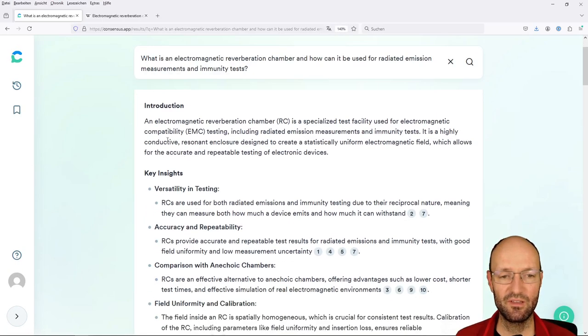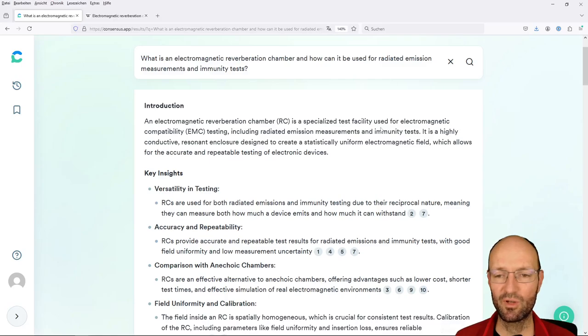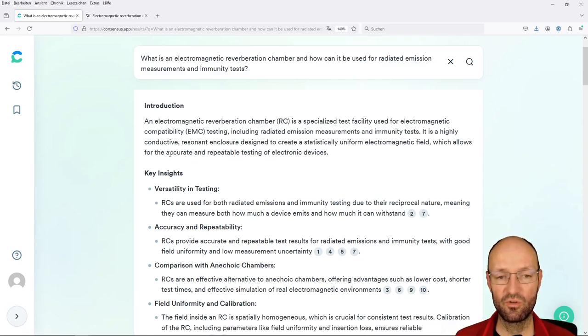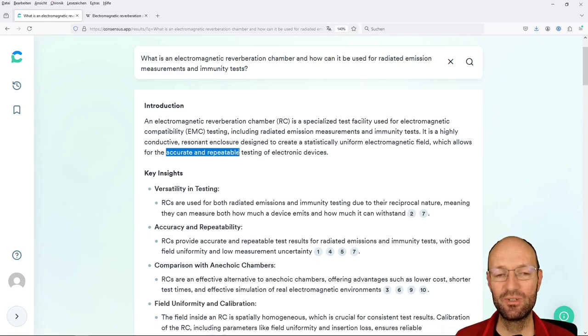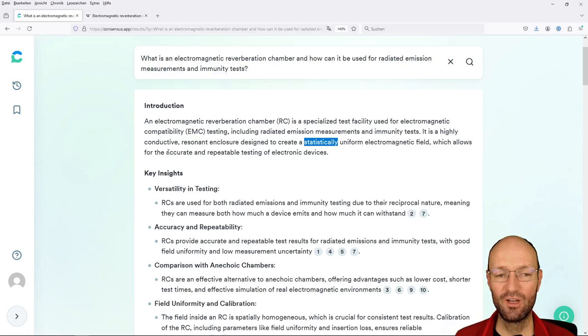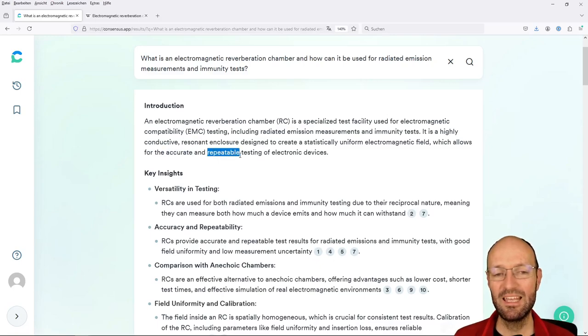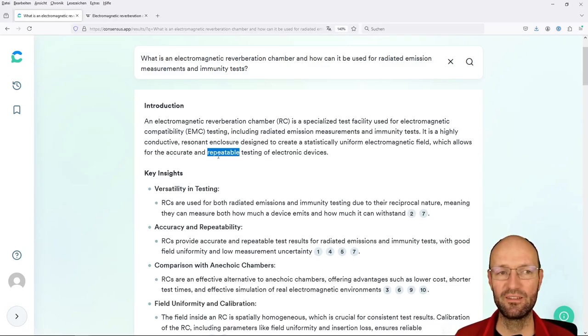Let me enlarge this a little bit. So it says as an introduction, a reverb chamber is a specialized test facility used for electromagnetic compatibility testing. This includes radiated emission measurements and immunity tests. It's repeating my question. And it is a highly conductive resonant enclosure designed to create statistically uniform electromagnetic fields. That's correct. Which allows for accurate and repeatable testing of electronic devices. And I would doubt and I would question the really accurate and repeatable because in the end, it's a statistic test environment.